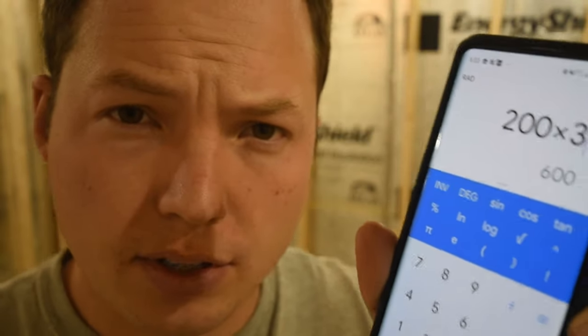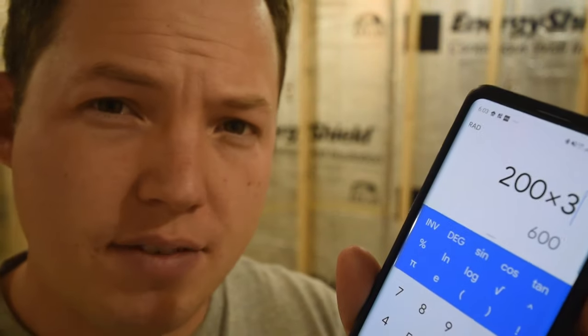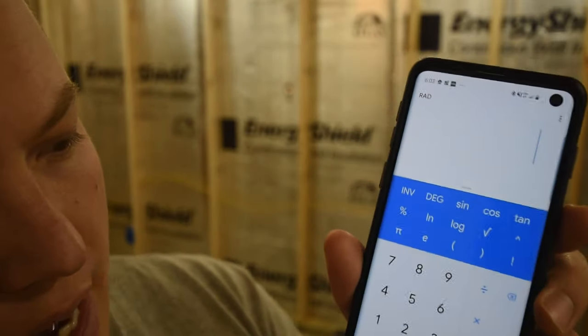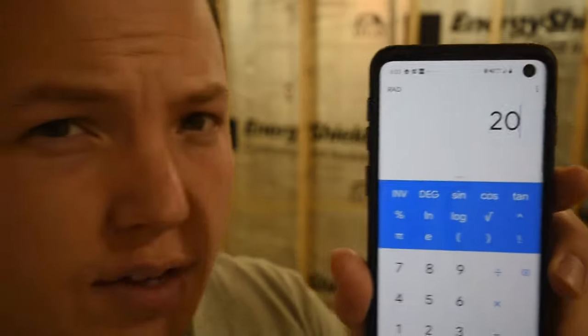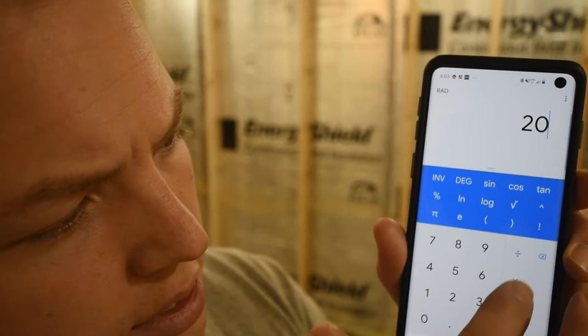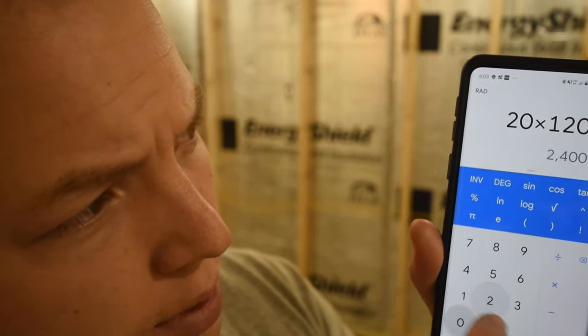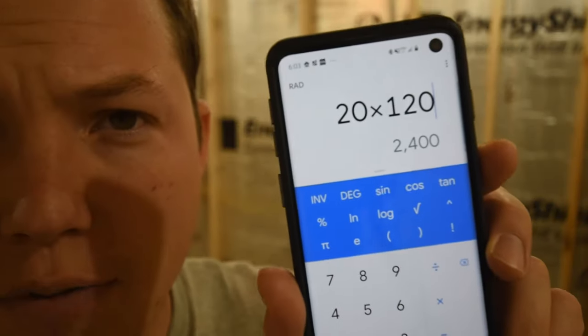Now if we look at our typical circuit, it's either going to be a 15 or a 20 amp circuit. If we assume that it's going to be a 20 amp circuit, we take 20 times the voltage of the circuit, which is 120 volts, so 20 times 120 gives us 2,400 watts.